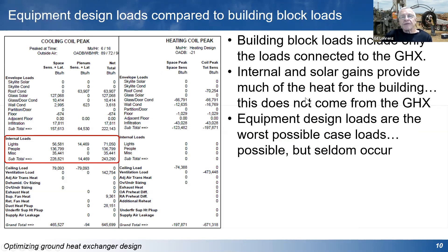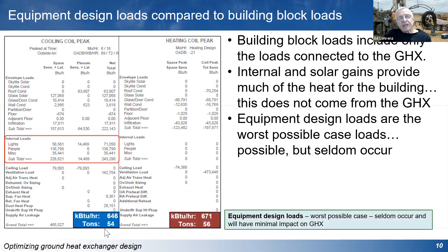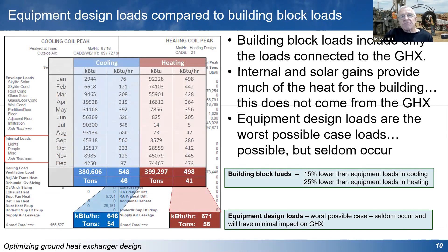One of the real things to look at when designing how much pipe needs to go in the ground is how you interpret the building heating and cooling loads. With design loads, this particular project ended up with about 54 tons of cooling and 56 tons of heating — kind of the worst case scenario on the hottest or coldest day of the year. But what the ground heat exchanger sees almost 99.9% of the time is often a lot lower. The block loads ended up being about 46 tons versus 54 tons of equipment, and 41 tons of heating rather than 56 — about 25% lower for heating and 15% lower for cooling.